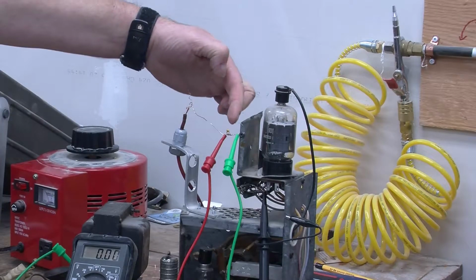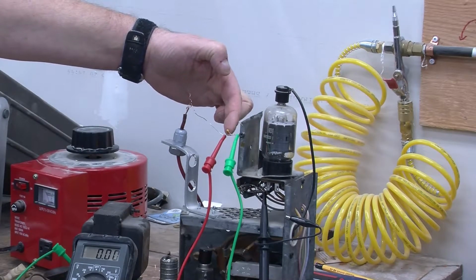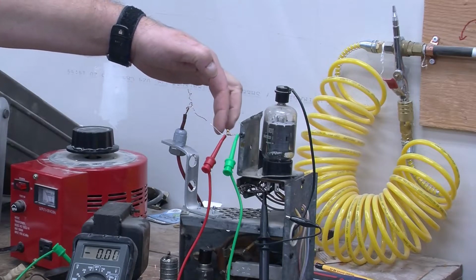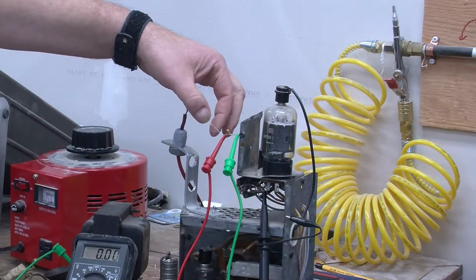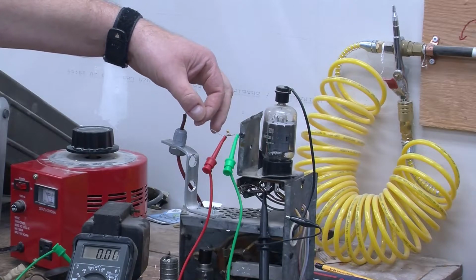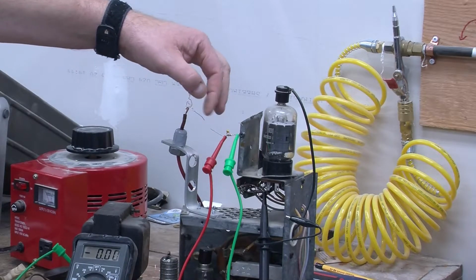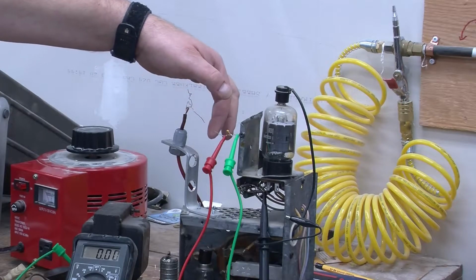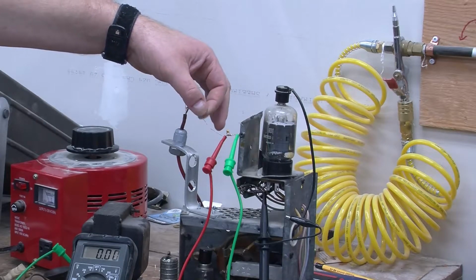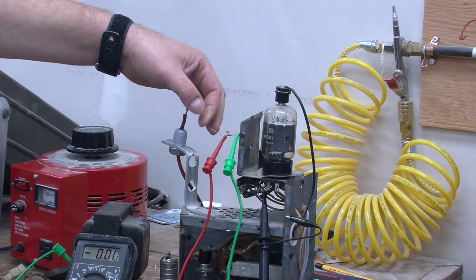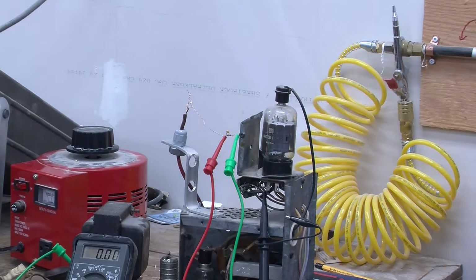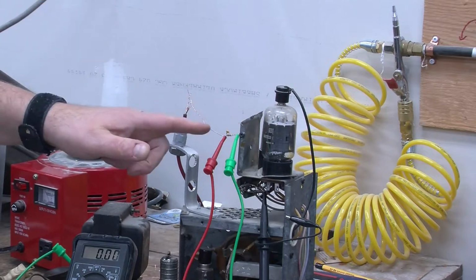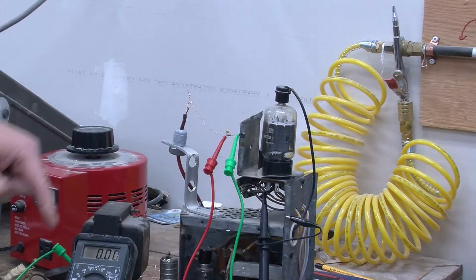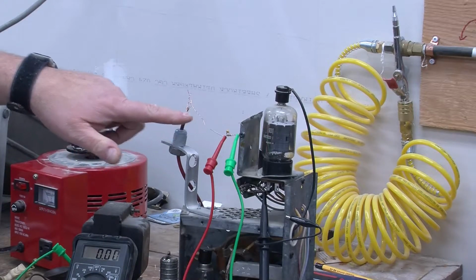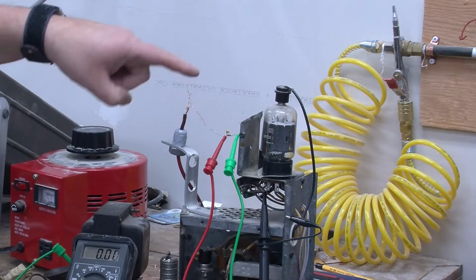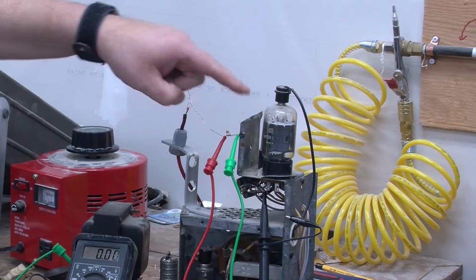The reason we have a capacitor here is to smooth out the little bursts of audio frequency energy from the static electricity device, which are at about 15 kilohertz. With a frequency cutoff of about 150 hertz, we should essentially just see DC on the voltmeter, which gives us the average current flowing from here to ground.